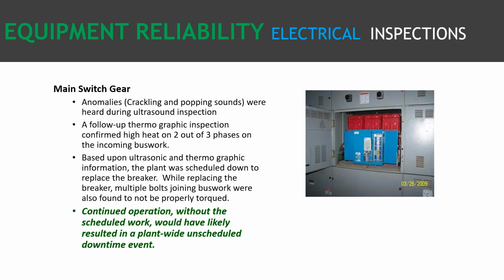They got the proper PPE, shut the equipment down, opened it up, and looked at it visually, but couldn't find anything. They did a follow-up thermographic inspection and identified some high heat on 2 out of the 3 phases. Based on the thermographic and ultrasonic inspections, they scheduled some downtime to replace the breaker, and while doing that, found some bolts holding the buswork together that weren't properly torqued. All kinds of problems identified through just hearing some cracking and popping.